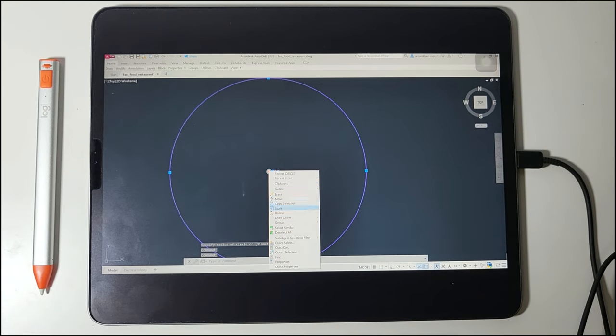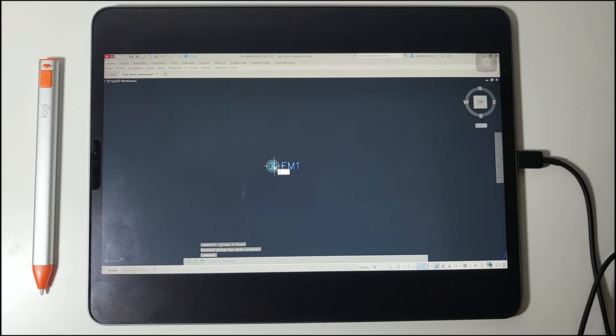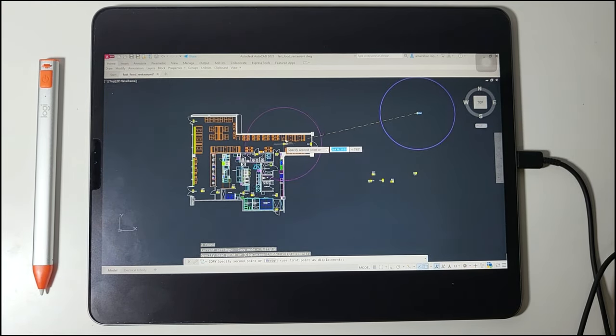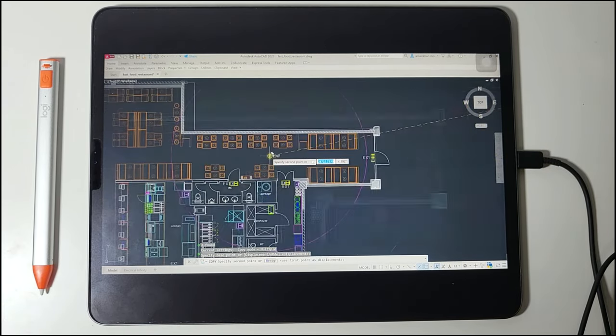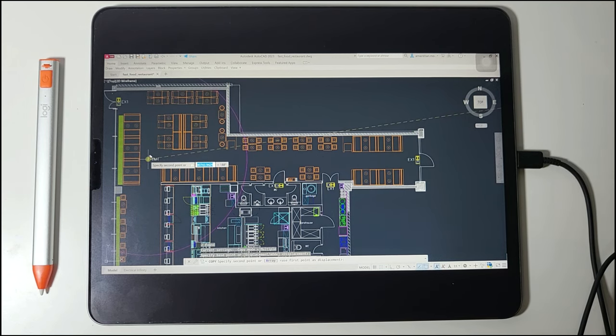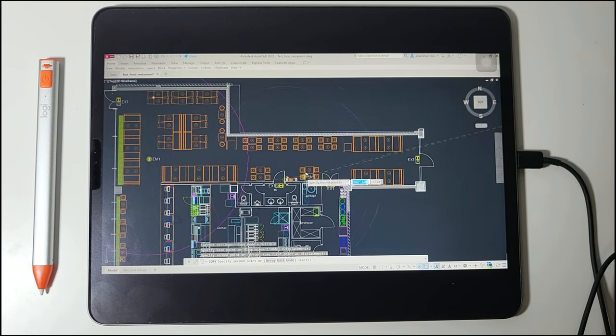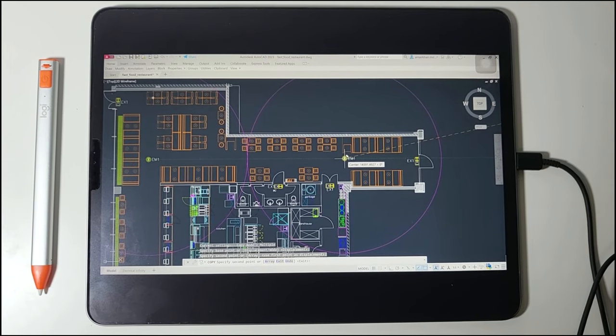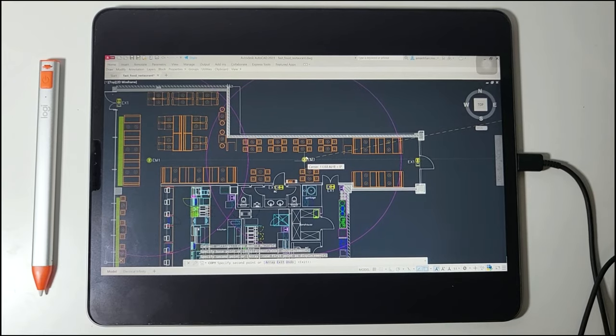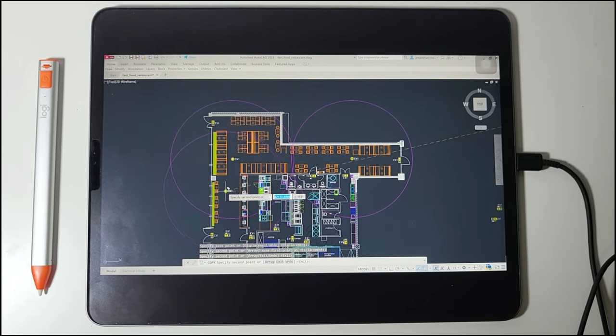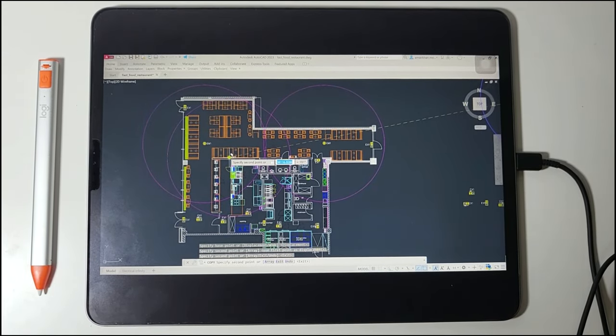I'm drawing a circle of 7.2 meters radius — 7,200 mm — and grouping them together to help place the emergency luminaires on the development site. Starting from the left side at the intersection of the restaurant corridors, I place the first emergency light at the center of the intersection, ensuring it covers the whole area. Additional luminaires are placed so the circles are touching, and care is taken that the distance from the exit sign is not more than 5.6 meters as per the manufacturer data sheet.